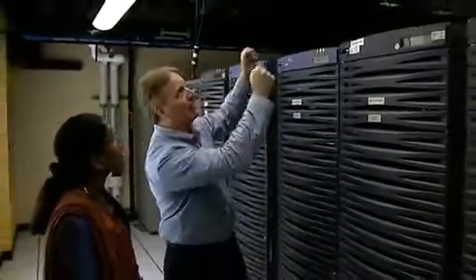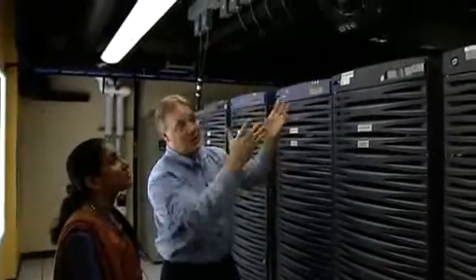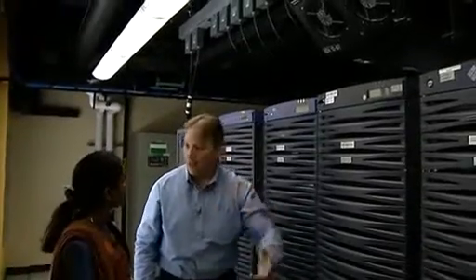This is refrigerant-based, and it's also modular. So now I can just snap it in, plug it into the refrigerant piping, and I have 10 kilowatts of cooling wherever I want it to be at. Modularity enables efficiency. It also enables agility for the company. So if I am able to now snap in the cooling, power, and connectivity components to expand or contract when I need to, and they're all efficient no matter what load is in there, then business climate can change and I can adapt to that very quickly.